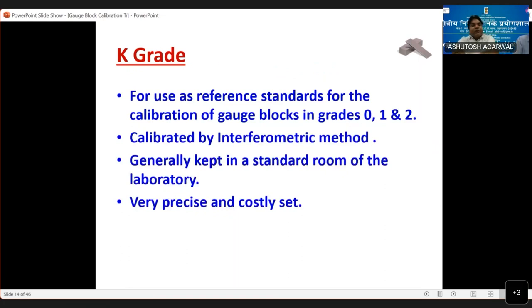Okay, so now come to the K grade. K grade is used as a reference standard for the calibration of gauge blocks in grades 0, 1, and 2. It must be calibrated only by the interferometric method, because that should be traceable to the primary standard. If we cannot do it by the interferometric laser method, then it becomes tertiary. It is generally kept in the standard room of the laboratory. Nobody can touch your masterpiece, only you.